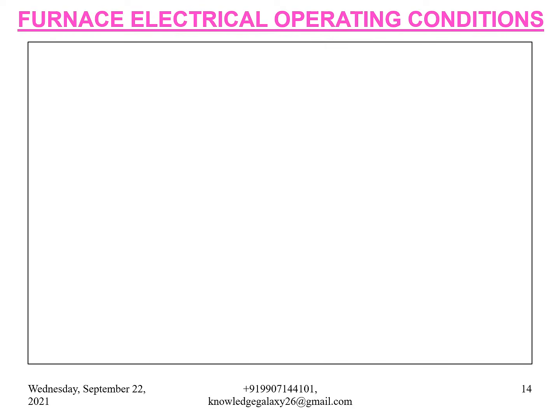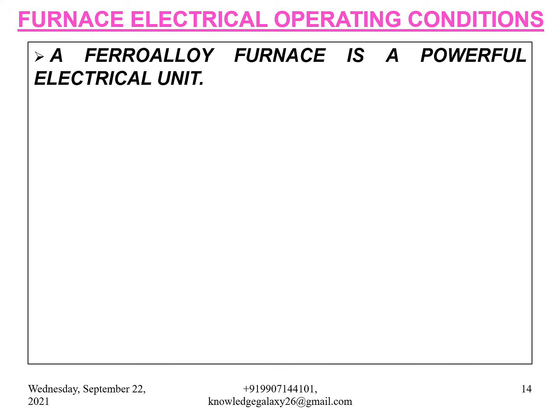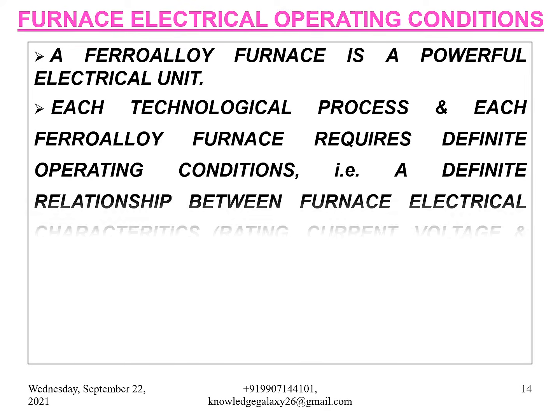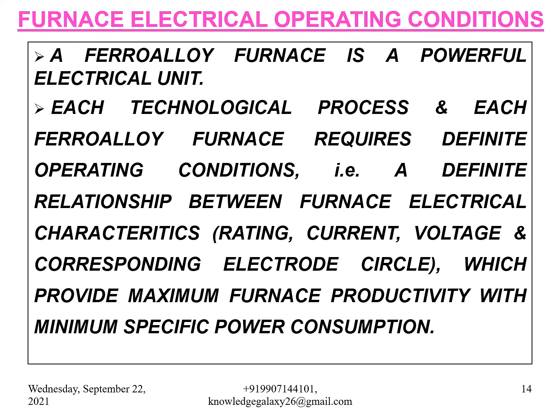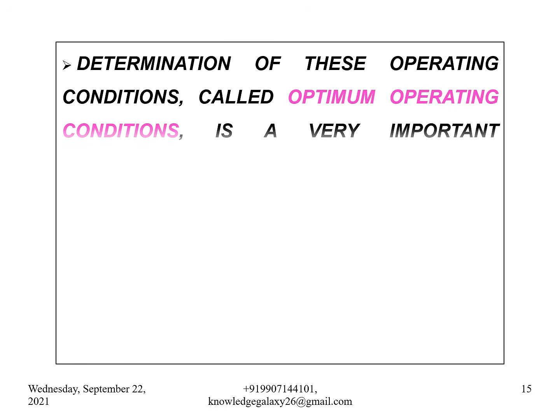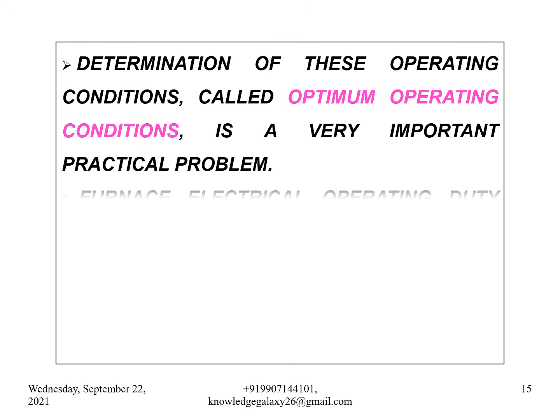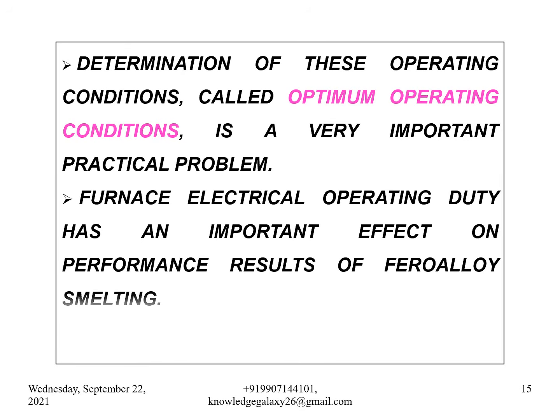Furnace electrical operating conditions. Let me explain this further. A ferroalloy furnace is a powerful electrical unit. Each technological process and each ferroalloy furnace requires definite operating conditions, that is, a definite relationship between furnace electrical characteristics, rating, current, voltage and corresponding electrode circle, which provide maximum furnace productivity with minimum specific power consumption. Determination of these operating conditions, called optimum operating conditions, is a very important practical problem. Furnace electrical operating duty has an important effect on performance results of ferroalloy smelting.